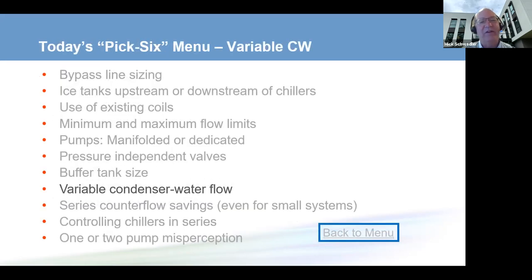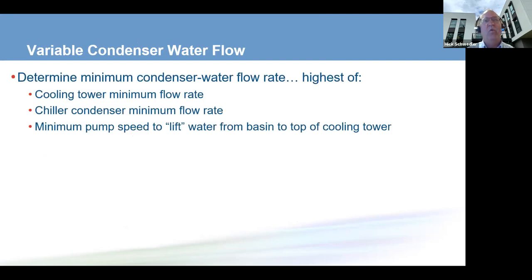So the last thing the Board of Governors picked in the Pick 6 menu was variable condenser water flow. And this is a question that I get asked a lot. Should we vary the condenser water flow rate? Well, when you start to vary the condenser water flow rate, the first thing you have to do is figure out how far we can slow down that flow rate. And it's going to be the highest of three different flow rates.